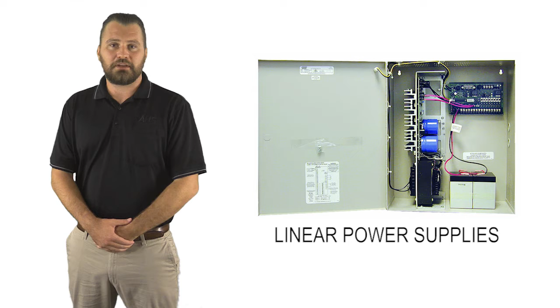There are two main types of power supplies for access control use. Linear power supplies can often be identified by having large transformers inside their enclosures. They take the AC input, typically 120 to 240 volts, and step it down with a transformer, then rectify and filter it into a DC output. This creates very clean and consistent power. Advantages of linear power supplies include simplicity, reliability, and low noise levels. The disadvantages: they are heavy, less efficient, higher cost, and they can run hot.